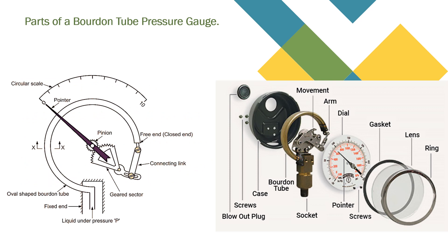Now let's see what are the parts of a Bourdon tube pressure gauge. It has an oval-shaped Bourdon tube with a free end and a fixed end. On the free end, a connecting link is provided, and that connecting link is connected with the geared sector. That geared sector is in turn connected with the pinion, which has a pointer that reads the scale on the circular scale.